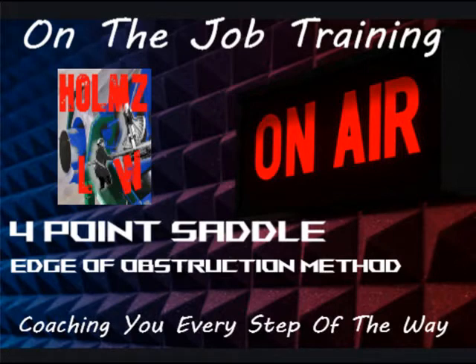Step 3, take that shrink value that you just calculated and add it to the value of the length to the edge of your obstruction. So let's just say you measured out a length of obstruction of 30 inches and you just calculated the shrink and it's a 1/2 inch. You're just going to add it to that 30, which is going to be 30.5. So you'll add that right into the length of the obstruction, and that's going to be your new length to the edge of the obstruction.